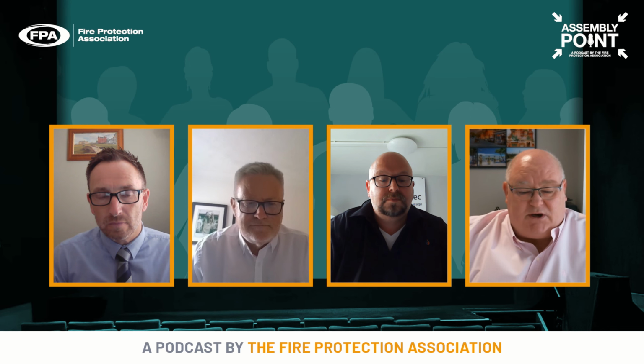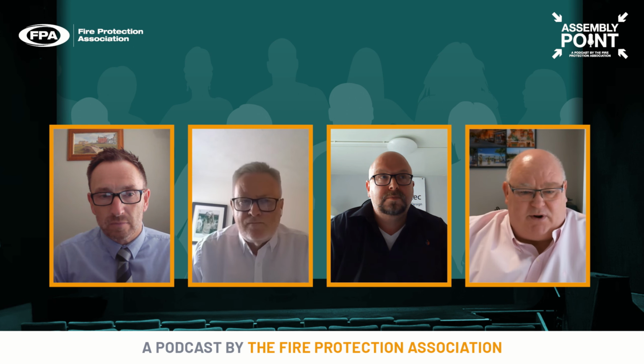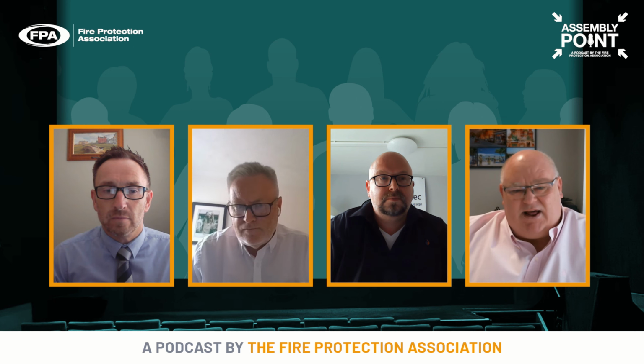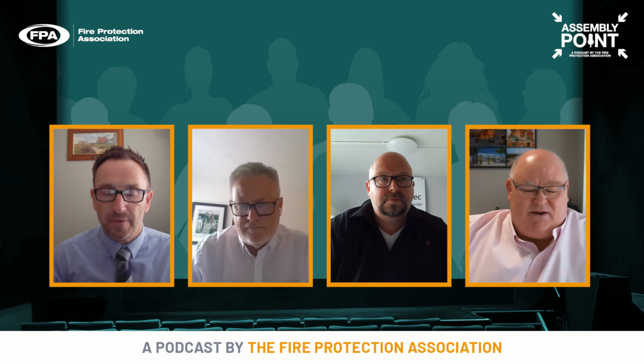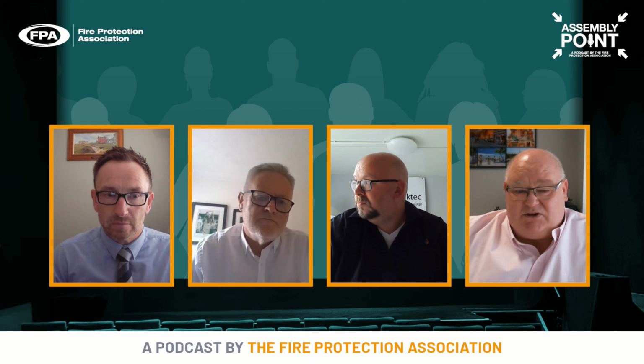And the recognised standard, you could say NFPA 750 or 14972 may meet that, but it really falls down on all the other areas because we find that either the components are not listed or the system's not been tested appropriately. And we've even seen cases where people have tried to claim it was tested by BRE. When I say BRE, they were actually tested at the BRE in a private test and not necessarily by the BRE. You could argue misrepresentation, but some people can't differentiate between the two.